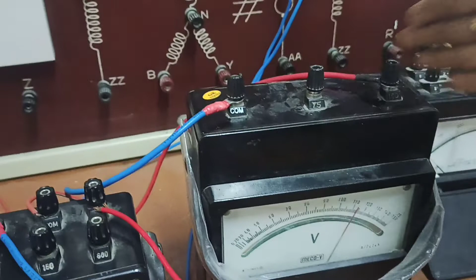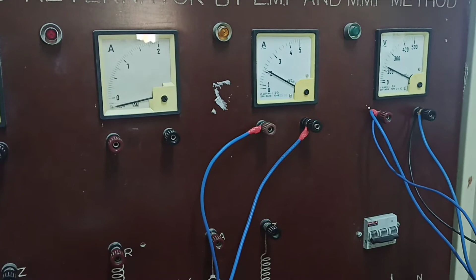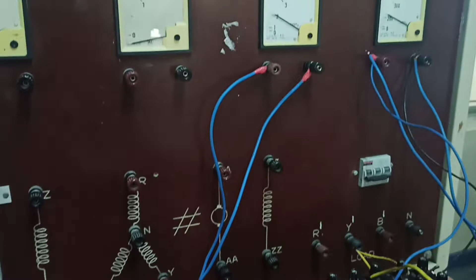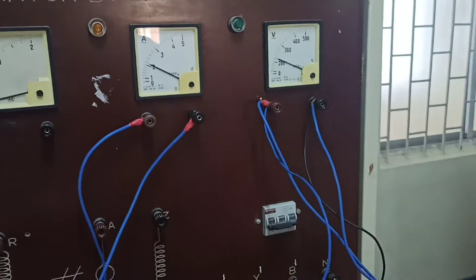Now we are going to apply different loads and we have to take different readings. First, switch on the 250 watts load. Note down the readings of the primary side voltmeter, wattmeter and ammeter. Similarly, note down the readings of the voltmeter, ammeter and wattmeter of the secondary side. So first we have applied 250 watt load for this.